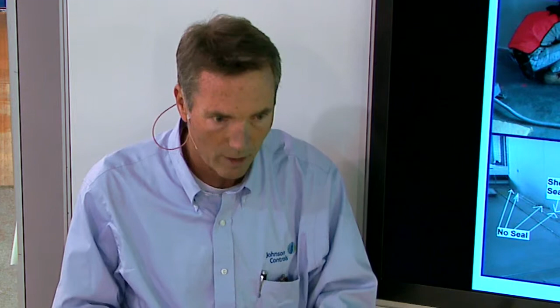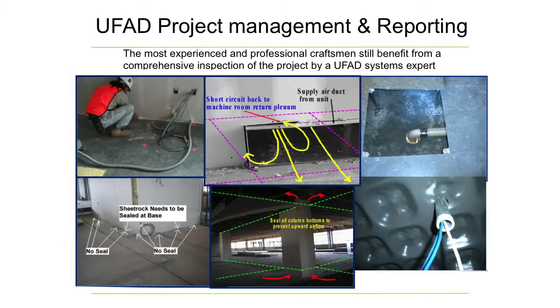Again, not rocket science, but more and more—here's a column as a poster child example. If we didn't seal that column, the plenum air would get into it, and now I have a conditioned column instead of a conditioned space. The thermostat would read the column, so it would say it needs heat in August in Houston. That's what we watch for, and it could be anywhere.